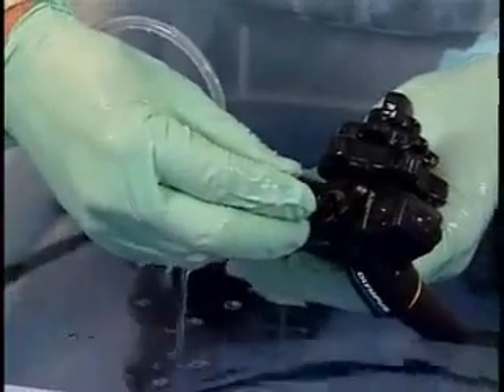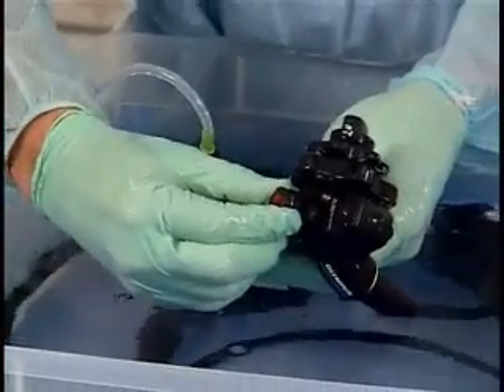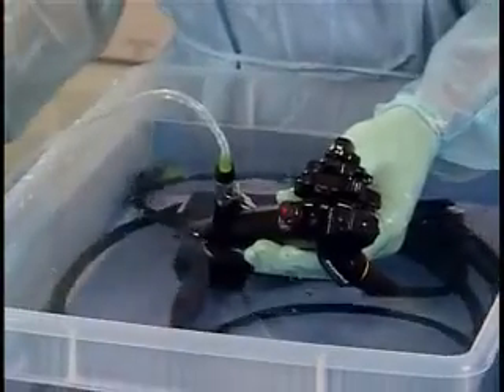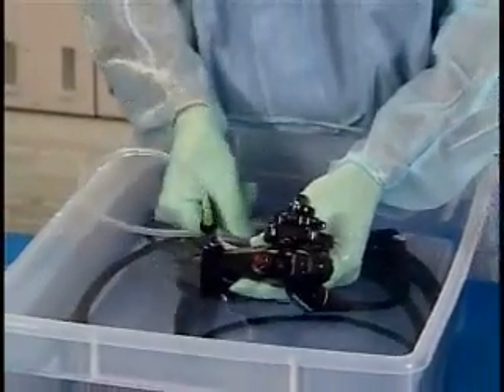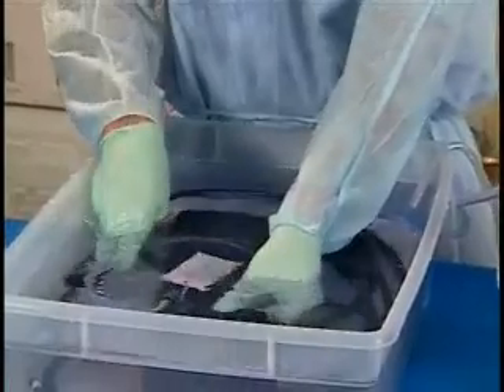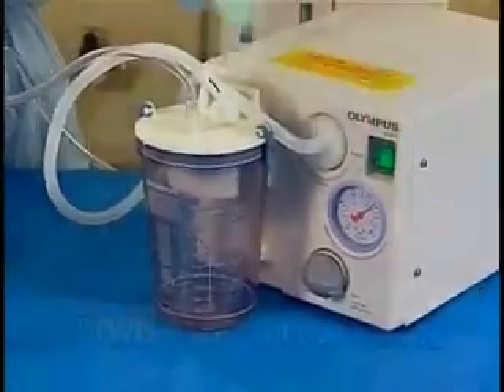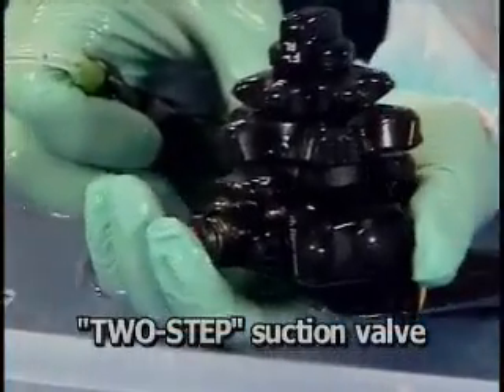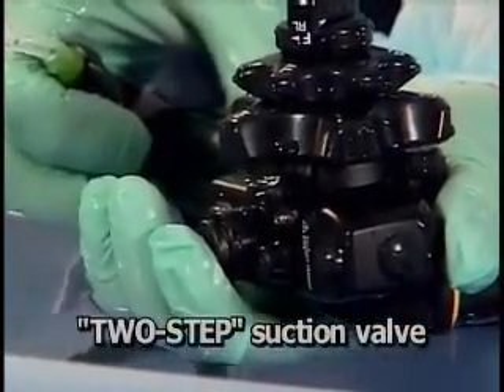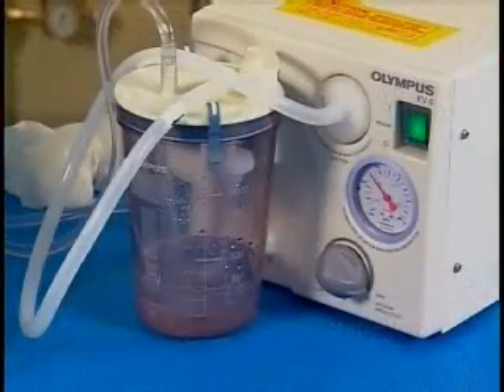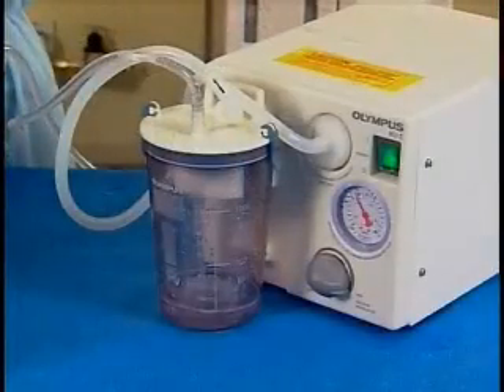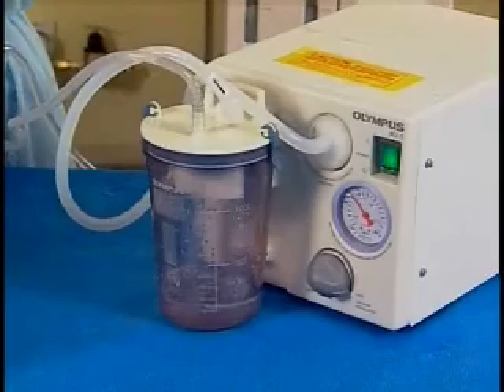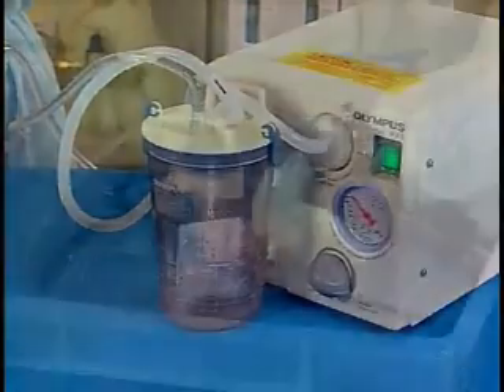Put the suction valve in the suction cylinder. Immerse the distal tip of the endoscope and suction cleaning adapter in detergent solution. Turn on the suction pump. Depress the suction valve to the first stage and aspirate detergent solution for 30 seconds through the instrument channel. Depress the suction valve completely and aspirate detergent solution for 30 seconds through the balloon suction channel.